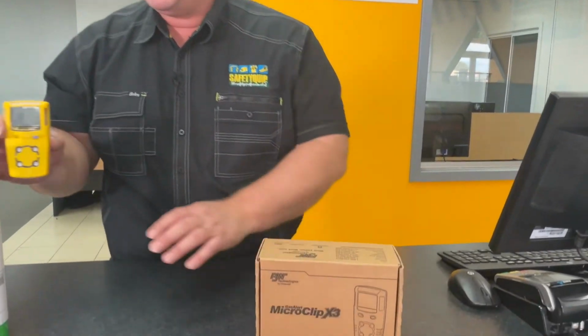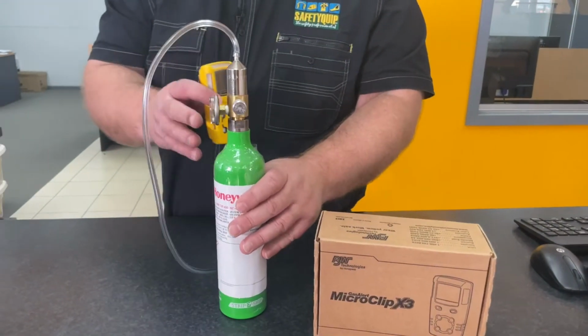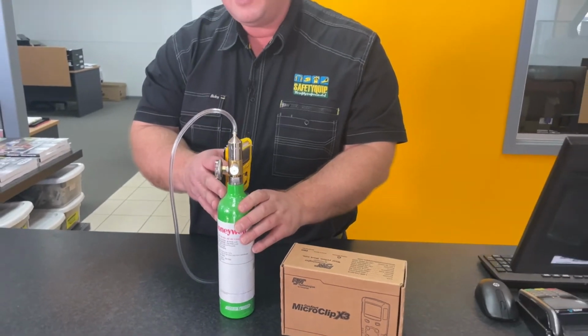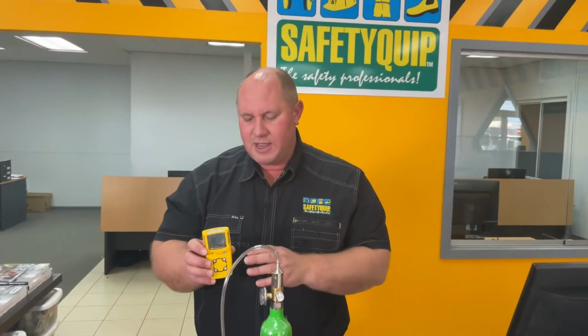Often you would calibrate it on an electronic dock back at the office. But yeah, if you're out in the field and need to calibrate it, these are the things that you need. So I'm going to run through the process. There's a cylinder of gas. Now that cylinder of gas must contain gases for each of the sensors that are fitted to the gas detector.